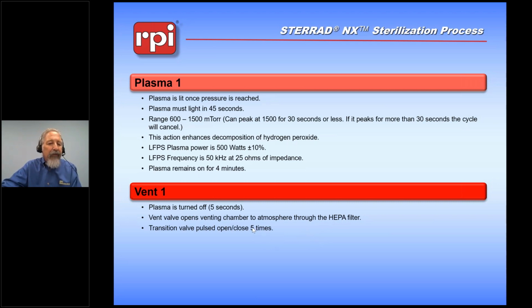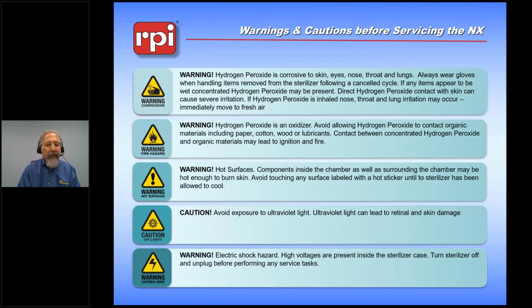And we will also double check the transition valve by opening and closing it an additional 5 times to make sure that it is not clogged and it is ready for the next cycle. The next cycle reproduces what we just saw. We do that twice per run. So in talking about hydrogen peroxide sterilizers, this does apply specifically to hydrogen peroxide sterilizers.